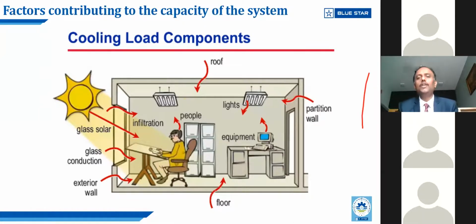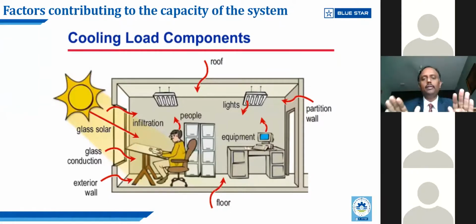When you become architects and are speccing in for some projects, you may have to give an air conditioning solution. When you call a HVAC person, you need to give all this information so he can design the system properly - where the building is coming, what the orientation is, the glass height, the lighting load, how many people will be inside, whether there's a floor above or below, whether it's an exposed roof. With this information, the HVAC engineer can do a proper heat load calculation and give you the right solution.